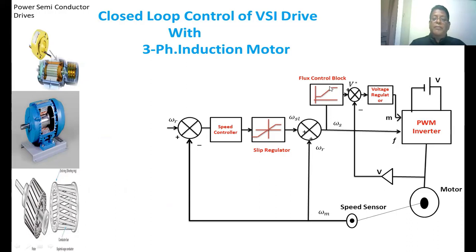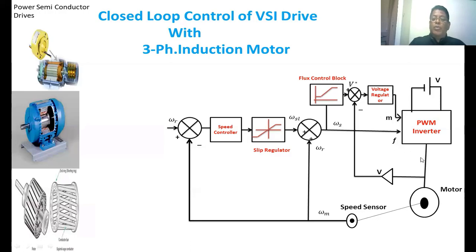The input to the flux control block is the synchronous speed. Dividing by 2π gives the frequency. For a given frequency, the flux control block generates a reference voltage. If the frequency is less than the rated frequency, then V/F is kept constant, and the reference voltage is set accordingly. This reference voltage is compared with the actual measured voltage. The error in voltage is given to the voltage regulator, which is also a PI controller. The output of the voltage regulator is the modulation index, which is given to the PWM inverter. If the modulation index changes, the voltage applied to the induction motor also changes.